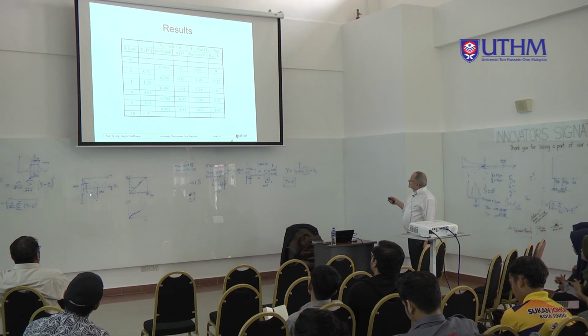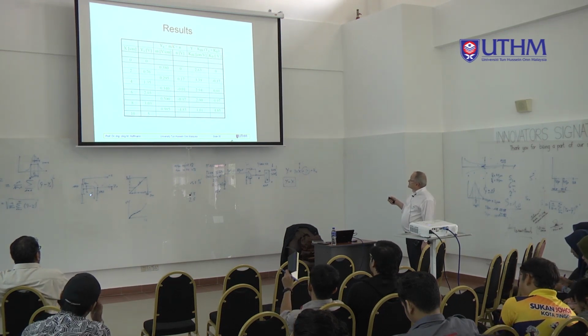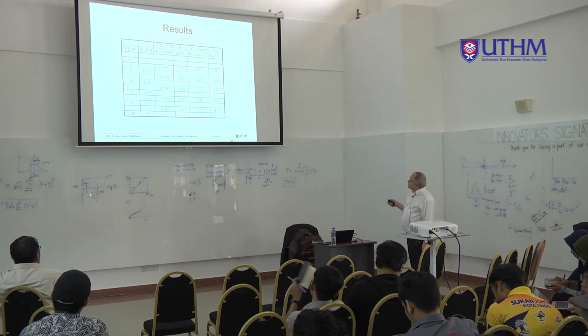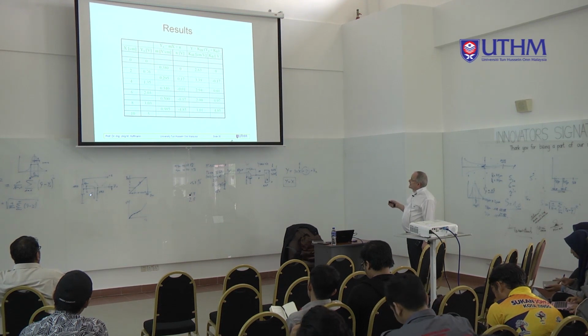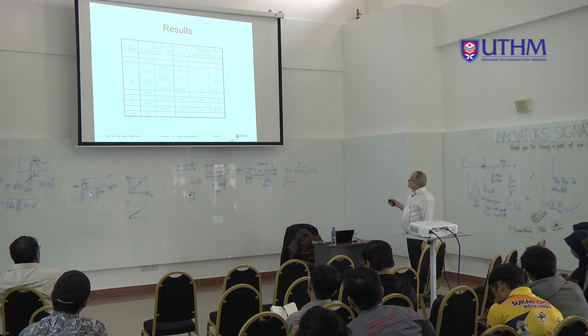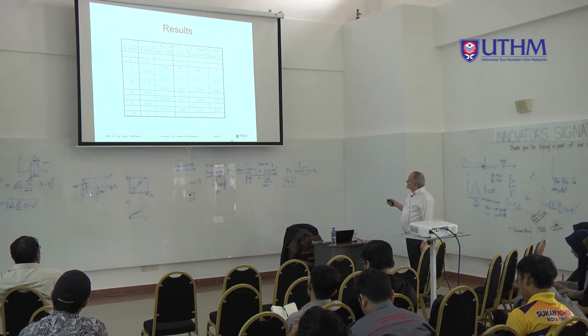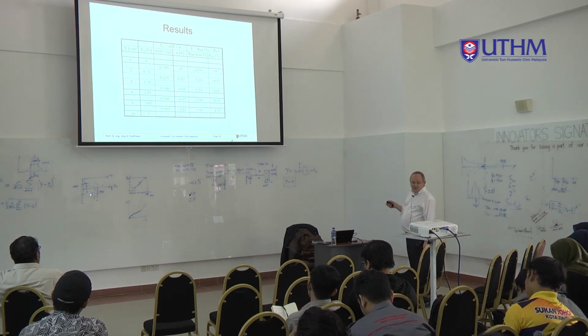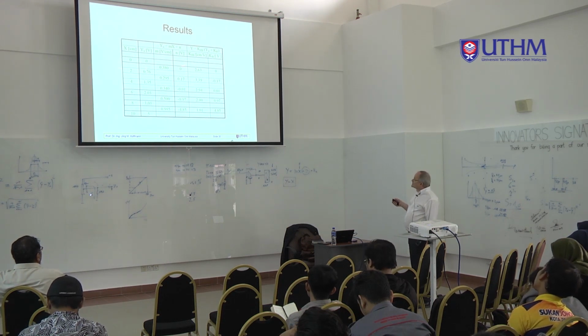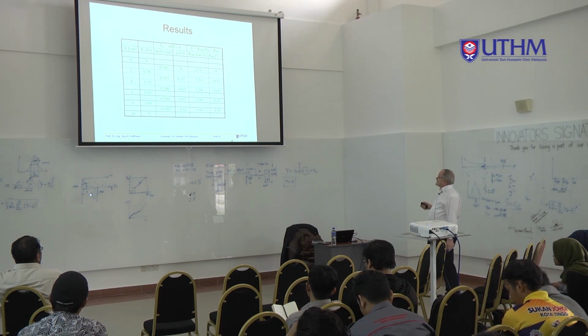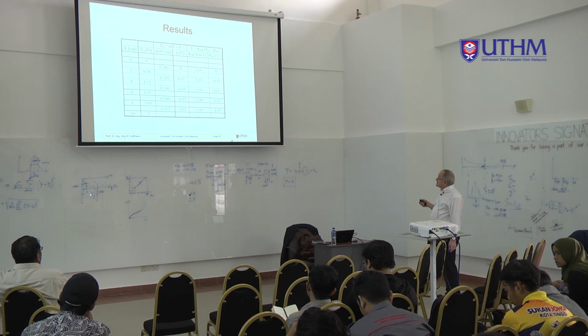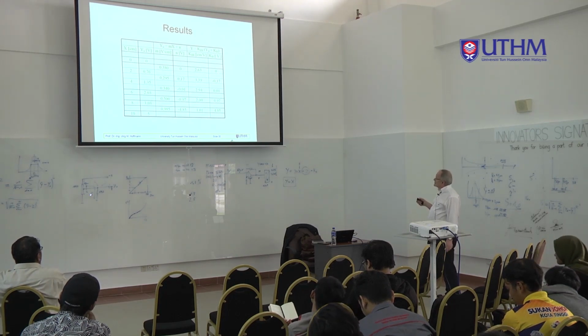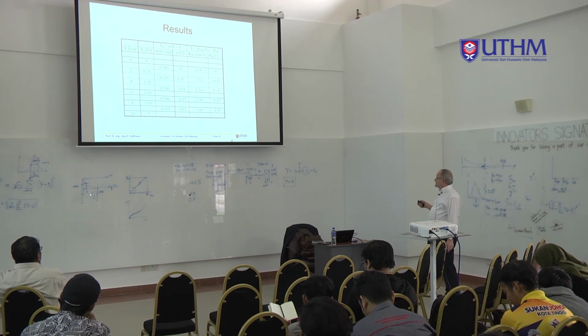So, and then we change the formula. n is y uncorrected minus m multiplied with x. And when you take this point and this m, it leads to 0. When you take this point and this m, it leads also to 0, because the line is going through both points. The line is the same through both points. So, and now we have to calculate the Km, the correction value. Km is 1 divided by m. Kn is minus n.